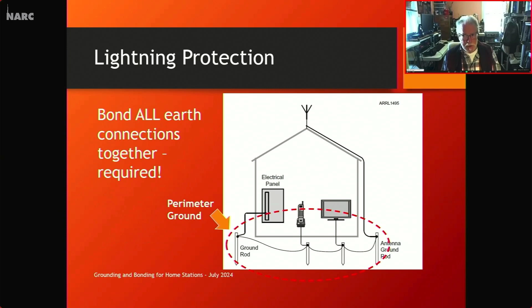And you don't want these low impedance paths to go through your station. Here's an example. Here's a tower with an antenna on the top of it, and Mr. Lightning comes along here and either hits the tower or it hits something close to the tower, and you get serious current flowing down the tower. Because of the inductance of that tower, you can get several kilovolts of difference between the top and the bottom. So here comes the lightning, and it flows along your cables, and you have this nice entry panel here, and some of the current will flow to this ground earth electrode here, but the rest of it will flow along your feed lines to your radios.